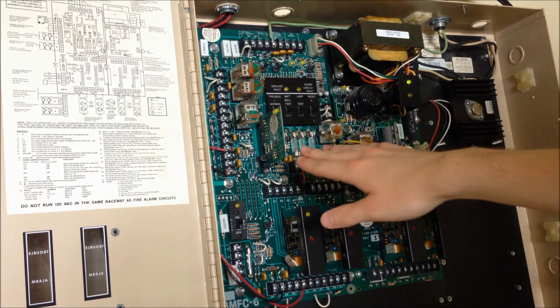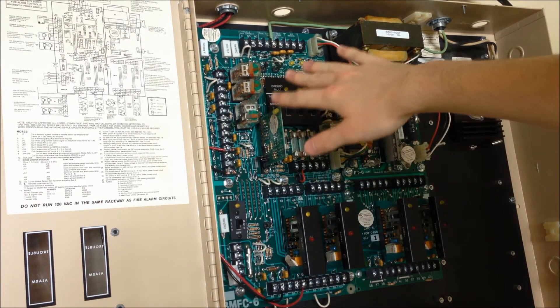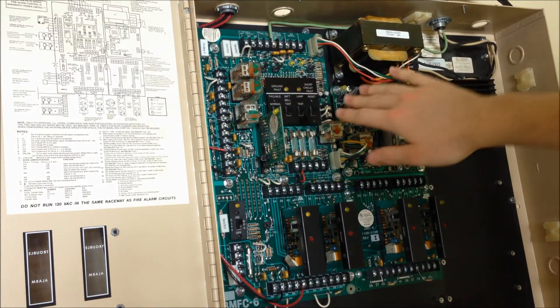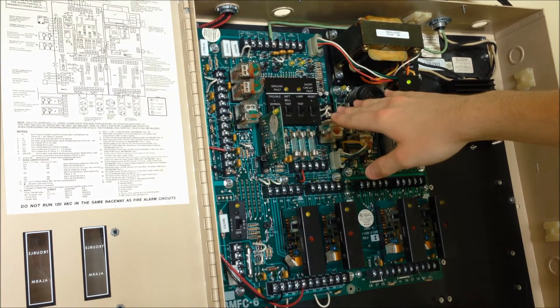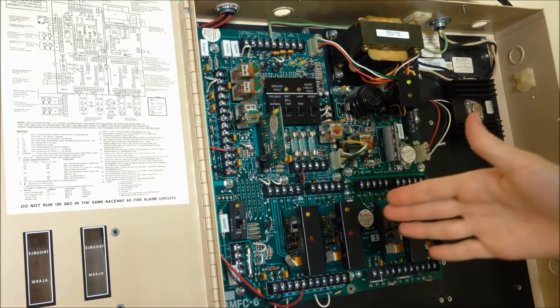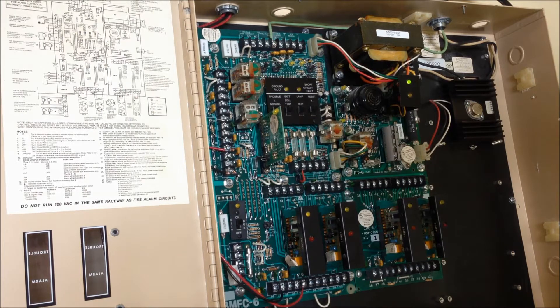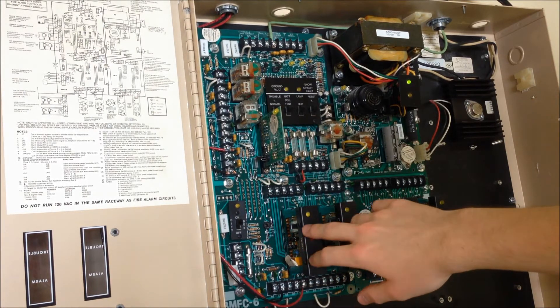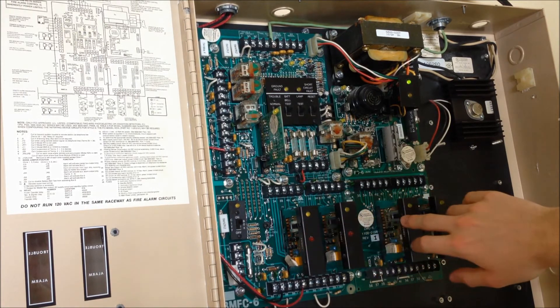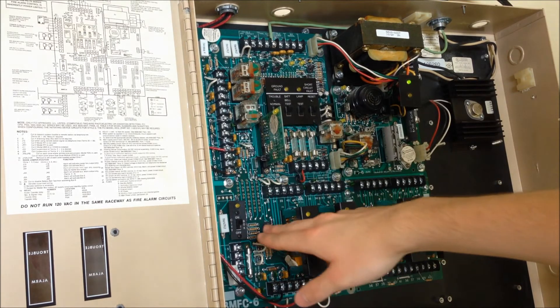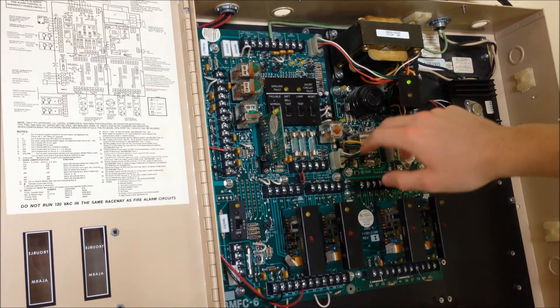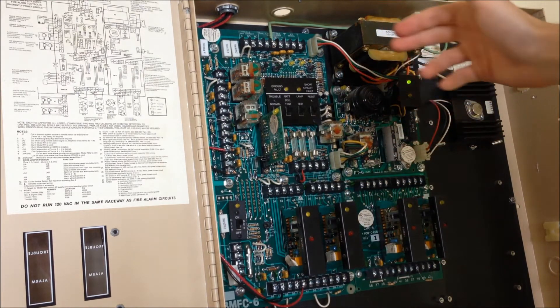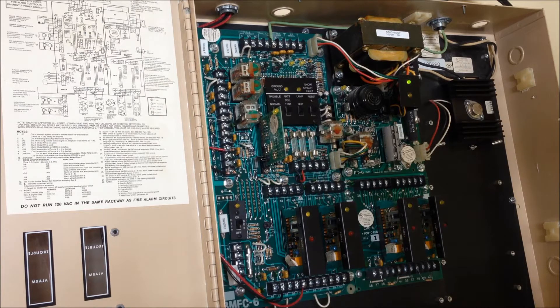Up here we have the signaling circuit card, some auxiliary relays for alarm and trouble. Right here we have what you could call the main control board area even though most of the controls and indicators are pretty spread out all over this whole panel. For example to silence the alarms you have to use the individual switches on the sides of these zones that were activated. We have the city box cut off over here then everything else is on that board at least for this panel's current configuration.